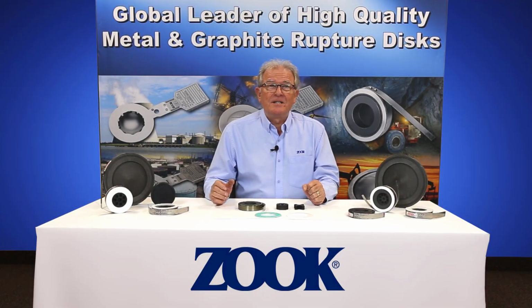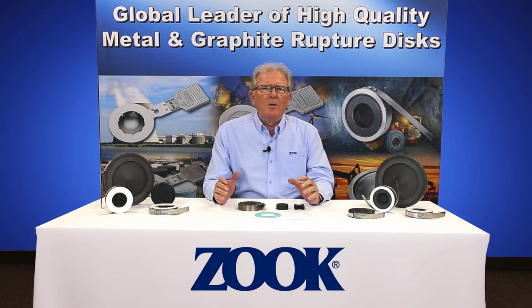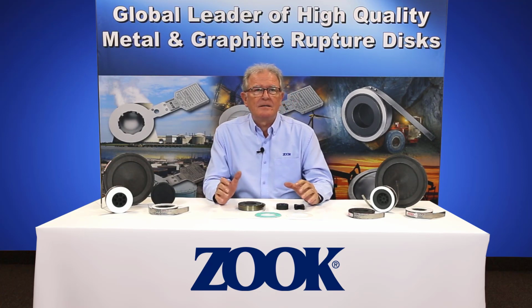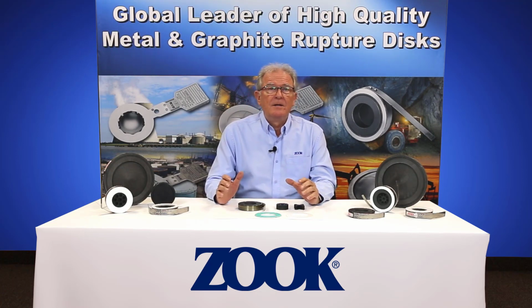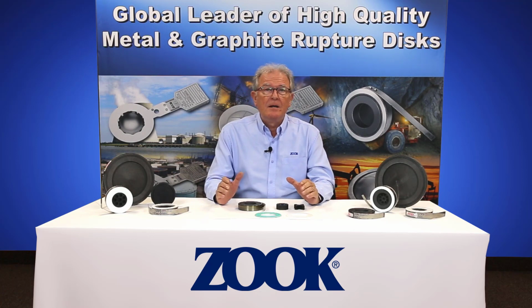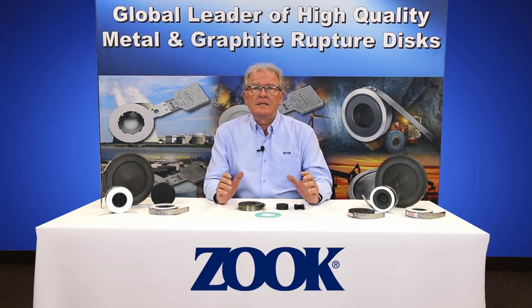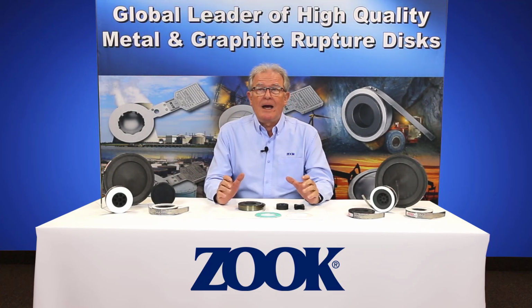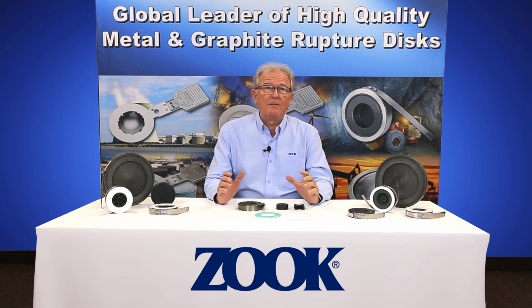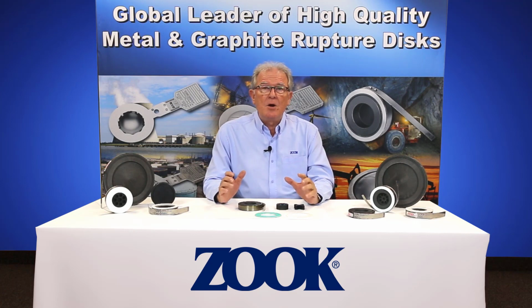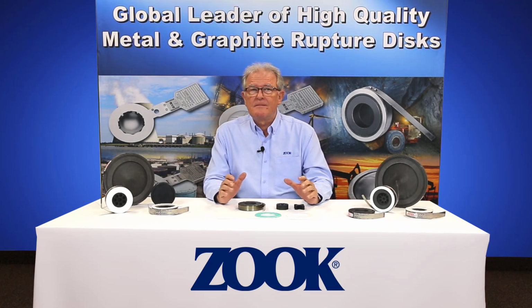The graphite mono design is highly suited for low to intermediate pressure burst ratings from 0.25 to 150 psi or 0.017 to 10.3 bar, and is available from 1/2 inch to 24 inch or 6 mm to 600 mm nominal bore pipe size.